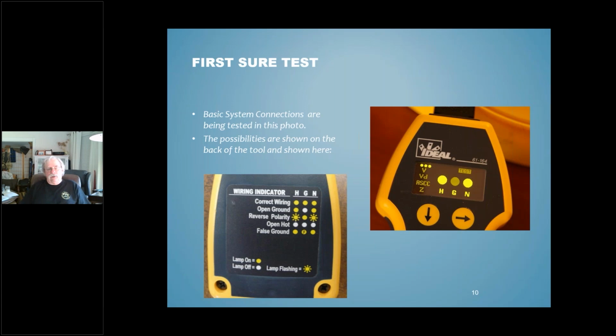In my experience, it'll actually work a little farther away than that, but you need to know what a false ground is, because if you're checking, for example, a shore power pedestal, not on board the boat yet, and I always check the shore power first, there may be a transformer on board or on the dock feeding the shore power receptacles that has a neutral to ground connection at the transformer, and it could conceivably be close enough to give you a false ground reading. I think the others are pretty self-explanatory. An open ground, also a very common occurrence, which is what gives us a lot of the problems that we actually have.